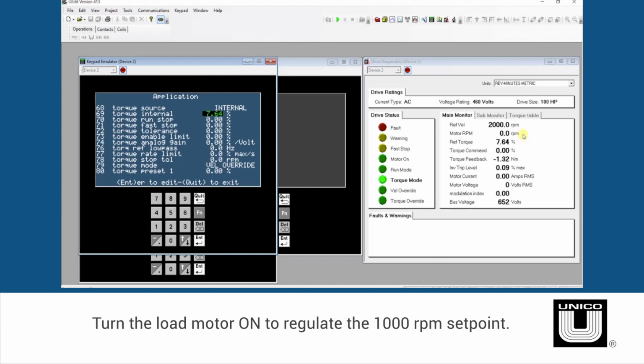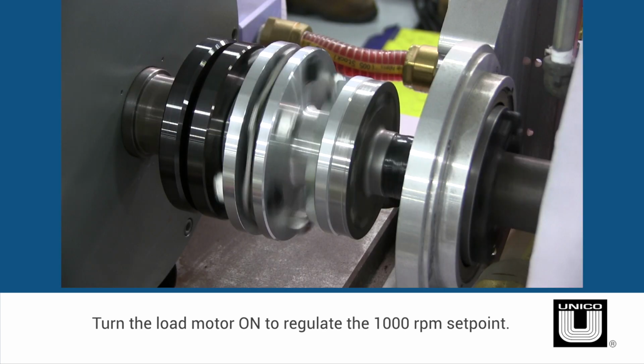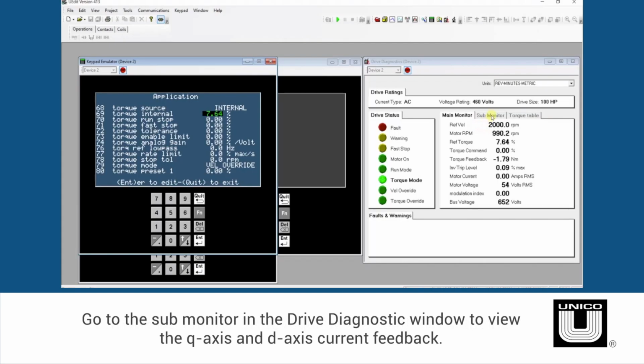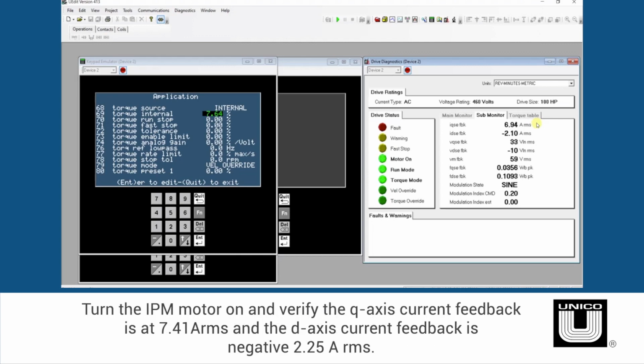Turn the load motor on to regulate the 1000 RPM set point. Then go to the sub-monitor in the drive diagnostic window to view the Q-axis and D-axis current feedback. Turn the IPM motor on and verify the Q-axis current feedback and D-axis current feedback. As you can see, the IQ current feedback is 7.4 and the D-axis current feedback is negative 2.2.